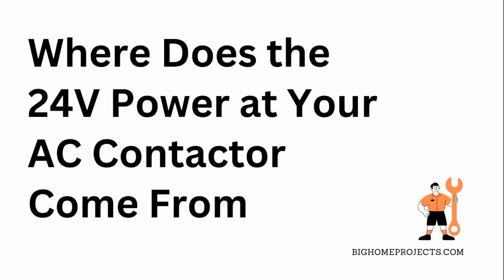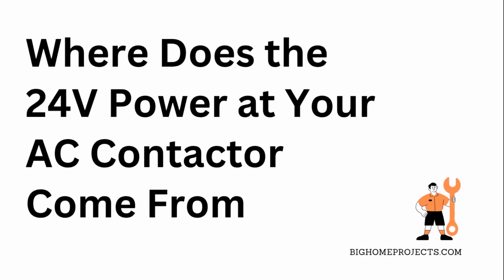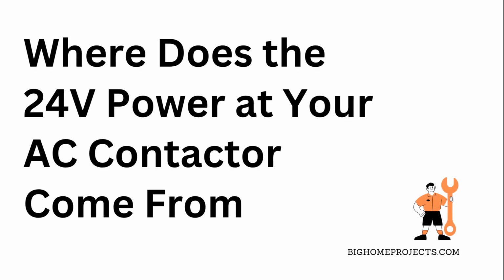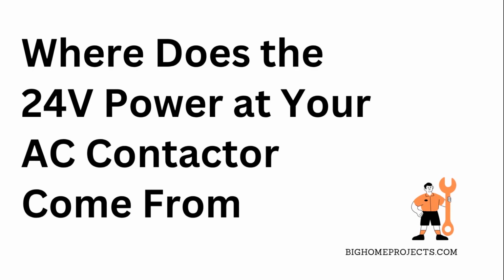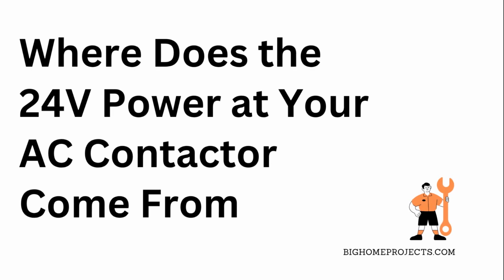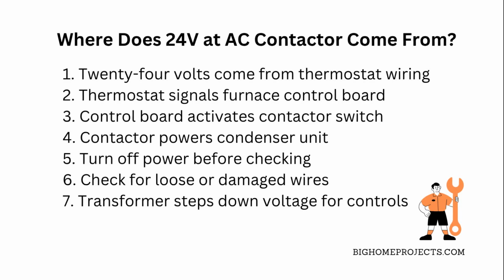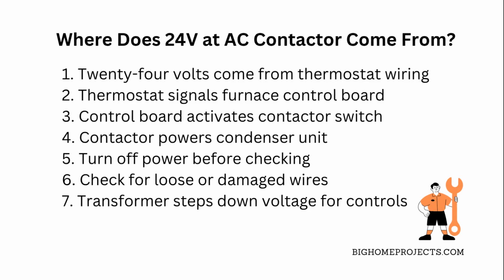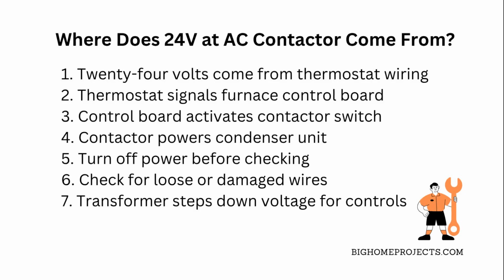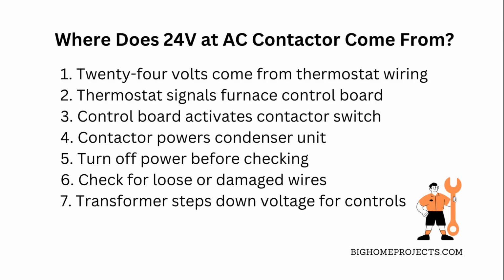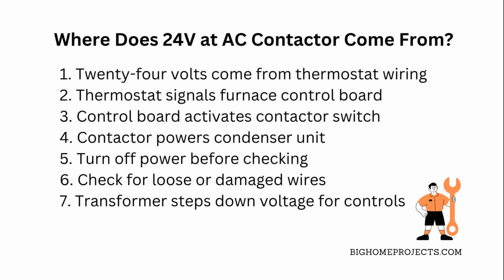All AC parts work together like a team, but figuring out where that 24 volt at the contactor comes from inside your house can totally confuse even seasoned DIYers. So, the 24 volt power at the contactor usually comes from your thermostat wiring, which is controlled by the furnace control board. When you set your thermostat to cool, it sends a signal through the red wire to the furnace control board. The control board then activates the contactor by sending 24 volts through the appropriate wires, closing the circuit to power the outdoor condenser unit.